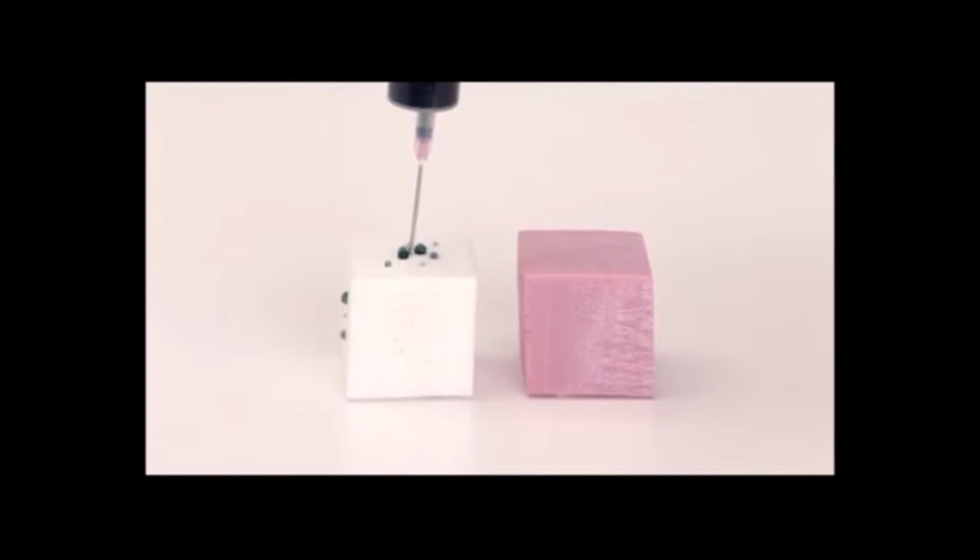With the EPS cell structure, the bead molding process leaves voids between beads where water can enter. Although the individual beads of EPS are closed cell, the voids between the beads can absorb significant amounts of water, which reduces the already lower in-service R value of EPS compared to XPS. It is important to understand the fundamental differences between the properties of XPS and EPS.